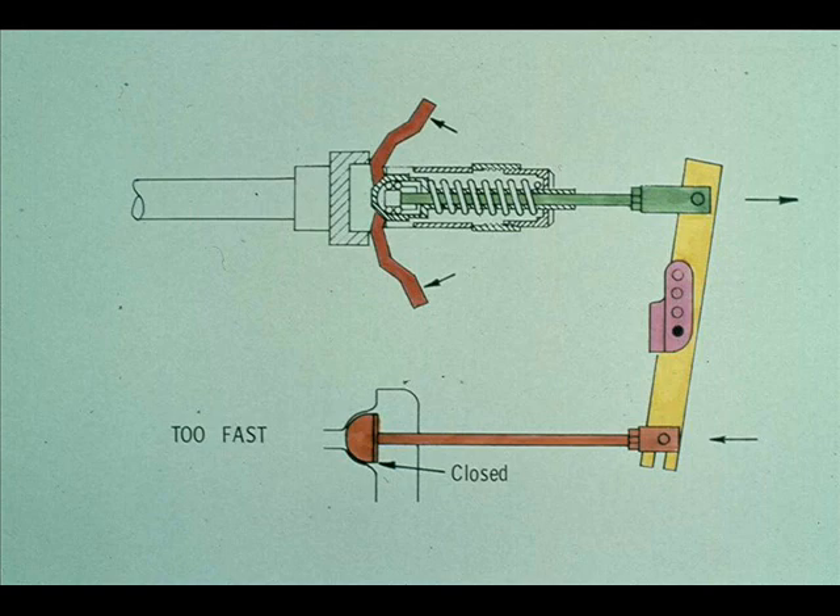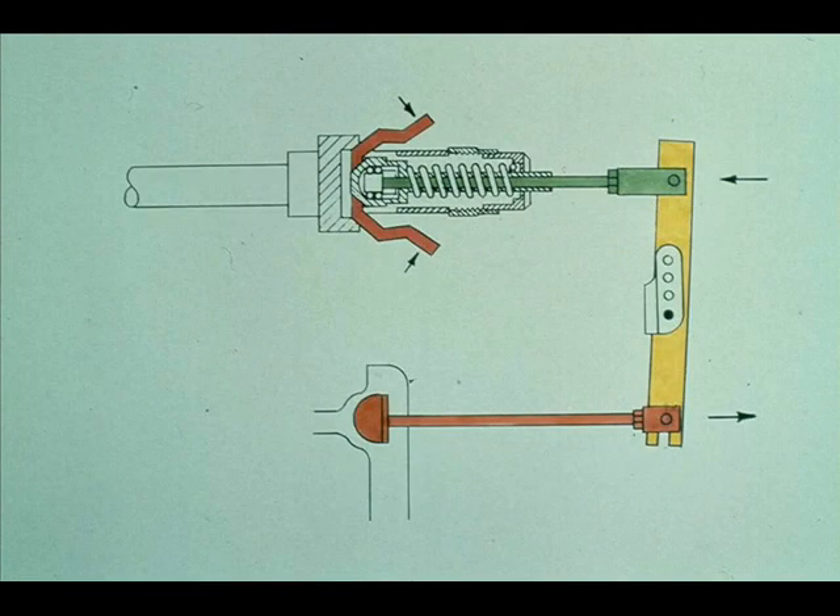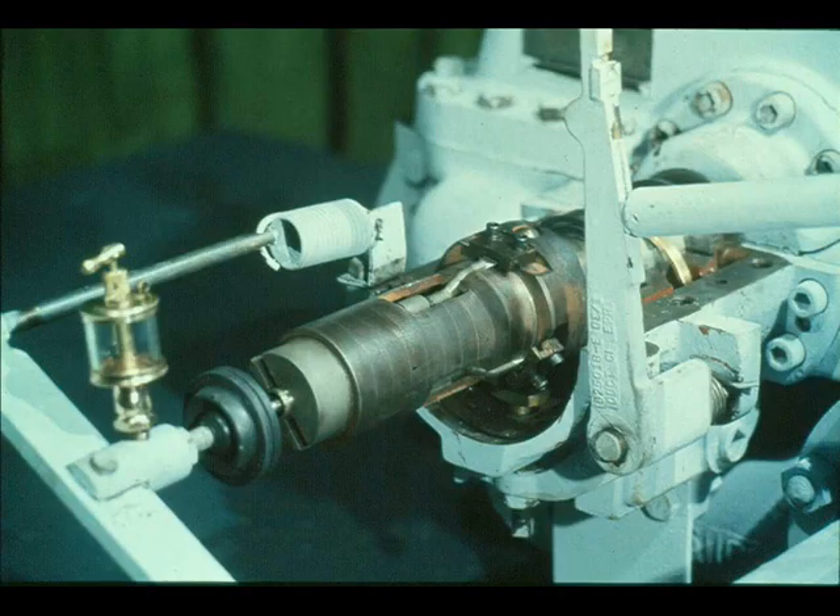This slows the turbine down. As the turbine slows down, the weights are pulled back toward the spindle by the spring, resulting in the governor spindle being pulled in, reopening the valve and feeding more steam to the turbine. The constant speed governor stops adjusting itself when it locates the operating speed for which it is set. That's the basic idea of the mechanical shaft constant speed governor. You are not expected to become an expert through these illustrations, but they should serve as a guide to understanding the basic principles of operation.